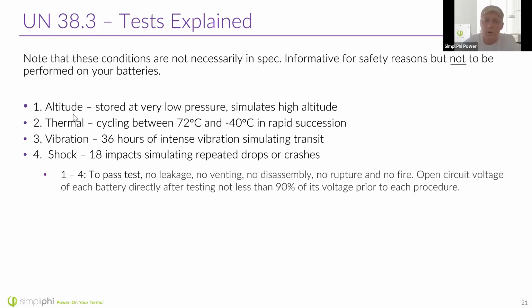One thing that is done to our batteries during this test by a third party is an altitude test. So this is going to store the batteries at a very low pressure, which simulates high altitude. It's going to cycle the batteries between 72 degrees Celsius and negative 40 degrees Celsius and do that in rapid succession. Going to give the batteries 36 hours of intense vibration simulating transit, so being in the back of a cargo van, and shock by repeatedly dropping the batteries to simulate a crash within a vehicle. To pass these tests, there can be no leakage, venting, disassembly, rupture, or fire, and they're going to check the open circuit voltage before and after the test, and it really can't change all that much.